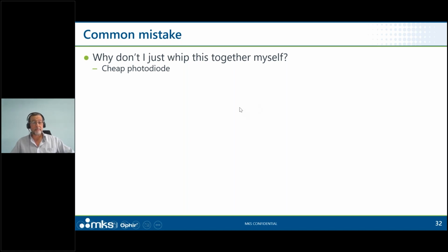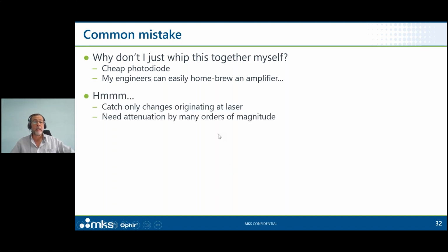So let's see. It's not such a big deal. That's true in some senses. If I'm going to base my instrument on a low power photodiode, that might mean that I want to only look at a small percentage of the beam that's coming out, which means if I'm going to put a splitter near the laser, I'm not going to catch changes that happen farther downstream. Photodiodes are very sensitive. That's a plus and a minus. It means that if I'm measuring a beam whose power is anything more than a couple hundred milliwatts, I'm going to need to start putting quite a bit of attenuation in there, and that could introduce all kinds of anomalies.